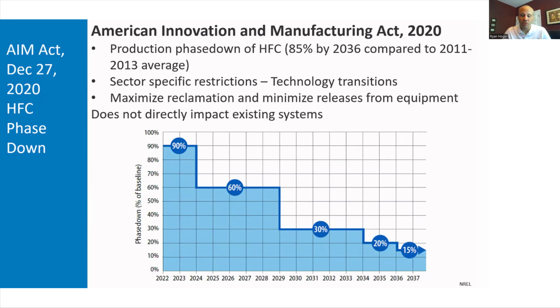So they can continue producing 410A, 407C, 134A indefinitely, but a much smaller quantity than they used to be able to produce. So it won't be readily available to everyone. That's a little bit different than R-22, which went all the way down to zero. Well, actually, I think it went down to 0.5%, but that's basically zero. So there's a little bit more buffer in this one, but it's happening in a faster window, whereas R-22 was a slow process. So that's what's happening with the refrigerants themselves.